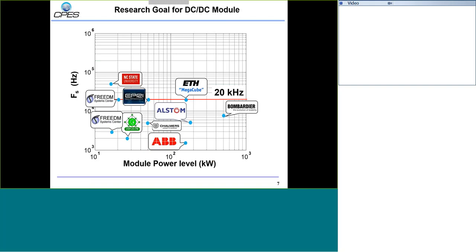Before building the hardware, we surveyed other people's work. We found that for today's DC-DC modules, most people limit the frequency below 20 kHz, with power levels from 10 kilowatts up to more than 100 kilowatts. Our target is a much higher frequency of 500 kHz, though we start with a lower power of 50 kilowatts per module. Eventually we can put modules in series and parallel to get high power, so starting with a moderate power module is sufficient.